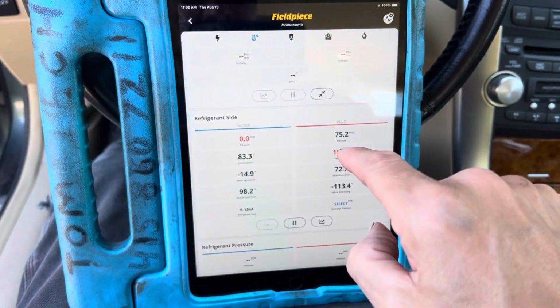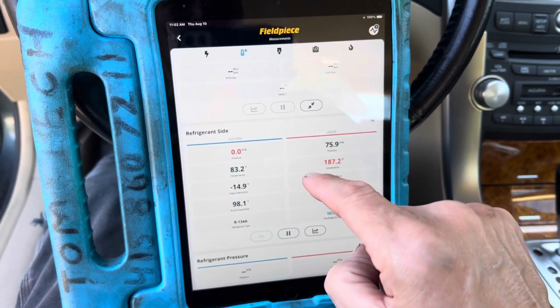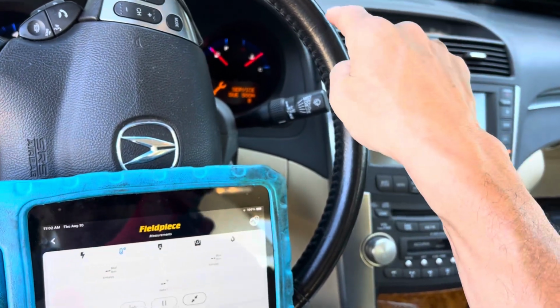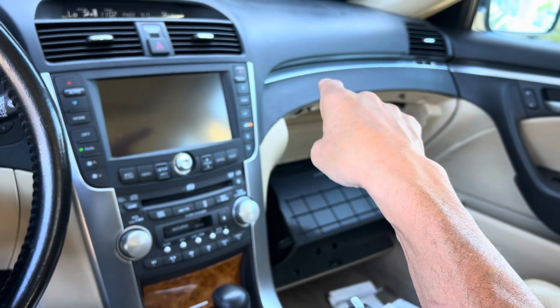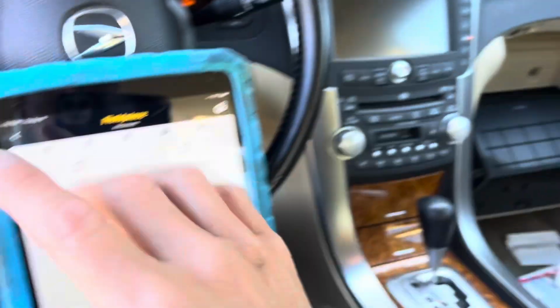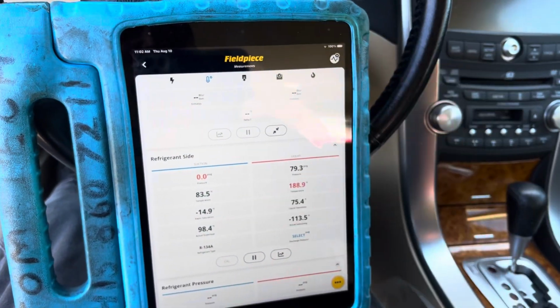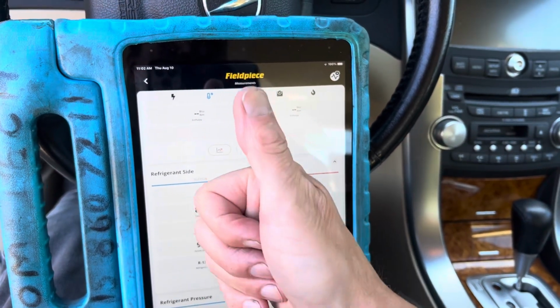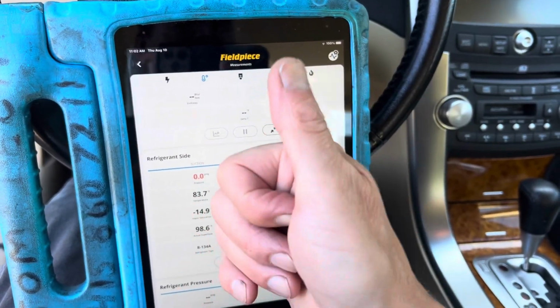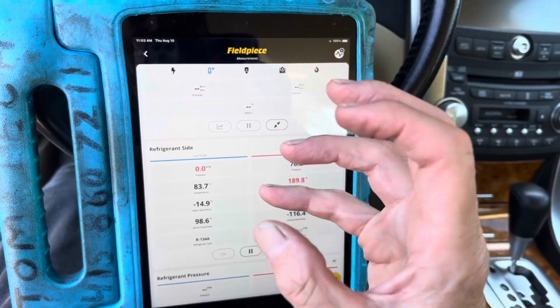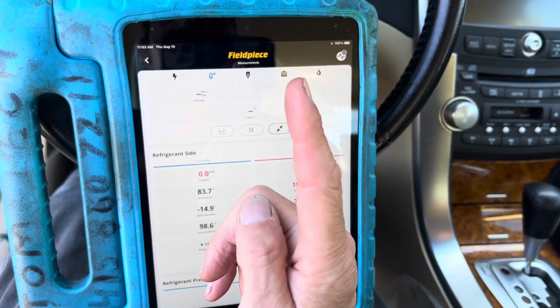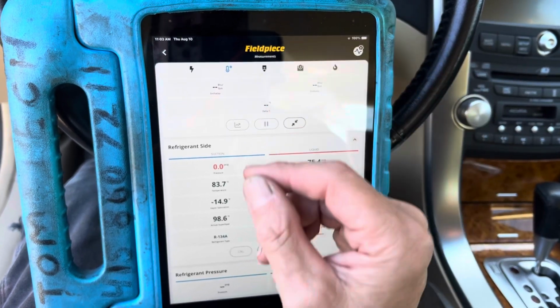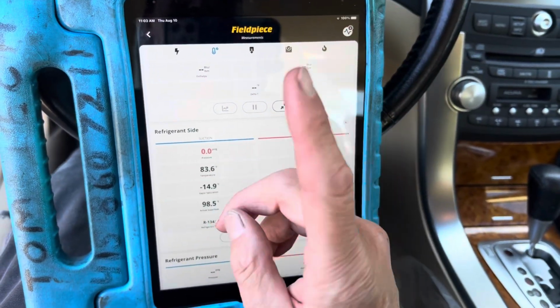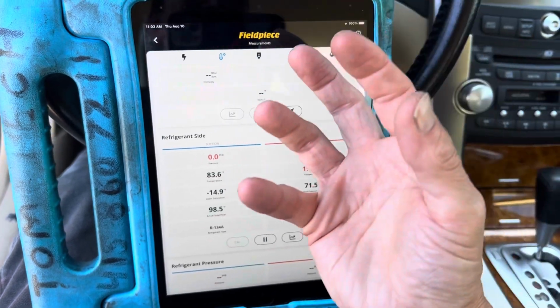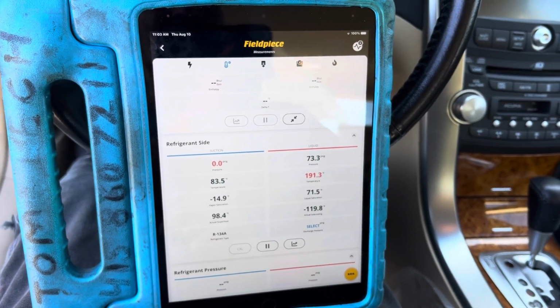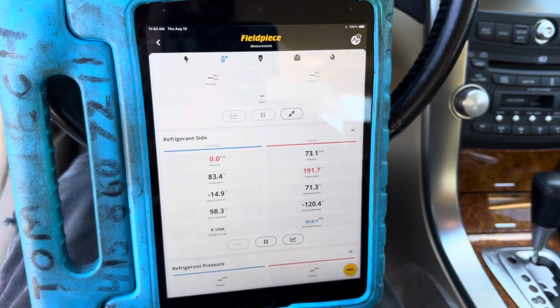But the customer or the technician did not know that all 4 ounces from the old compressor and system are entirely trapped up inside the evaporator. So now you have 8 ounces of refrigerant oil in the whole system, and they're wondering why there's cooling problems, maybe a vibration or a humming or a harmonics noise because of the high compression, because it's trying to, I'm going to say this and piss people off, compress a solid. Yes, a liquid is a solid. Let's not get technical on the physics here. But okay, it's a liquid, but can you compress water inside your cylinder in your engine? Go ahead and try that.